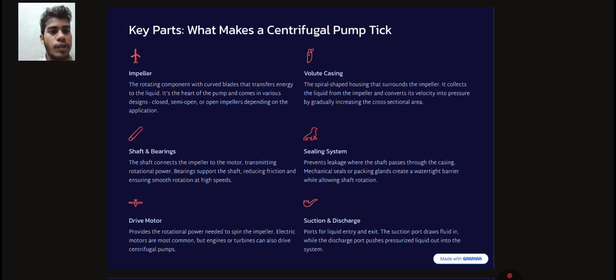Sealing system prevents leakage where the shaft passes through the casing. Mechanical seals or packing glands create a watertight barrier while allowing shaft rotation. Suction and discharge ports. Liquid enters and exits through them. The suction port draws fluid in, while the discharge port pushes liquid out into the system.